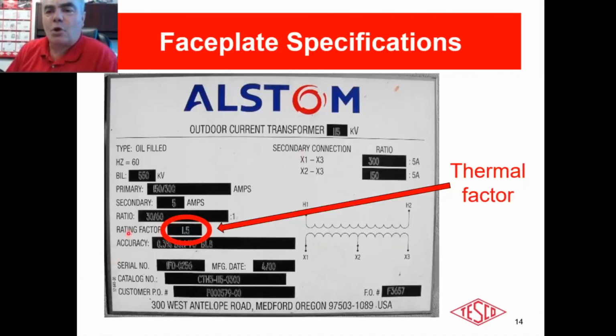On every faceplate, it's called a rating factor. In this particular case, it's relatively low, 1.5. A lot of times you'll see a rating factor of up to 4.0. Rating factor is a bit of a misnomer. Its true name is thermal rating factor, okay? Thermal rating factor. What the heck does that mean? That means that on this particular transformer, if I've hooked it up as a 300 to 5, I can very safely put 450 amps through the primary and have no problem whatsoever. If I start to go above 450, I will start to overheat the transformer.